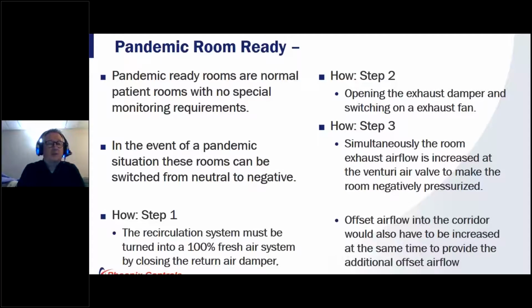The pandemic ready rooms, like I said: in the event of a pandemic, we can switch those neutral pressure patient rooms into being pandemic ready, a whole suite of them. And how do we do that? Well, the first step is patient rooms are allowed to recirculate, right? They can recirculate air up to 60, 80%. The recirculation system must be turned into a 100% fresh air system by closing the return air damper.